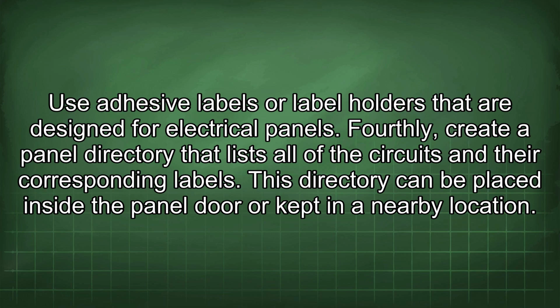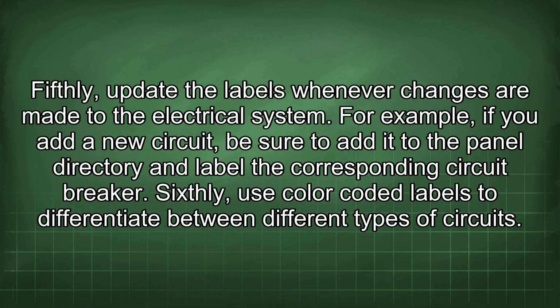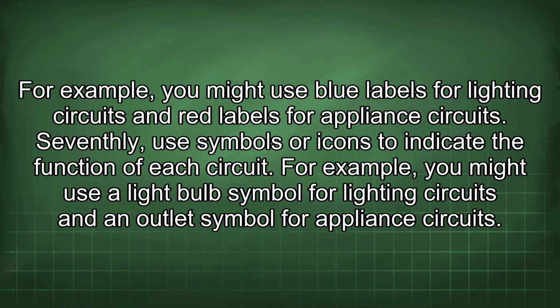Fourthly, create a panel directory that lists all of the circuits and their corresponding labels. This directory can be placed inside the panel door or kept in a nearby location. Fifthly, update the labels whenever changes are made to the electrical system. For example, if you add a new circuit, be sure to add it to the panel directory and label the corresponding circuit breaker. Sixthly, use color-coded labels to differentiate between different types of circuits. For example, you might use blue labels for lighting circuits and red labels for appliance circuits.